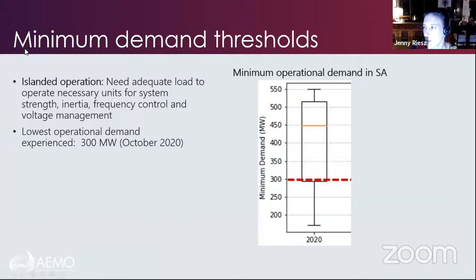The second issue that we've been looking at is simply around having enough demand to keep online the minimum units that we need, the large synchronous units, to supply all the essential system services. So we need a certain number of big units online to provide system strength, inertia, frequency control, and voltage control in particular. This figure here is showing you the range of load that we need in that South Australian region to keep on the minimum units that we need to supply the combination of services that's necessary. Some of those unit combinations involve much larger units, and we need up to about 500 megawatts of load. Other unit combinations have much lower minimum loading requirements, and we could get down to about 200 megawatts of load.